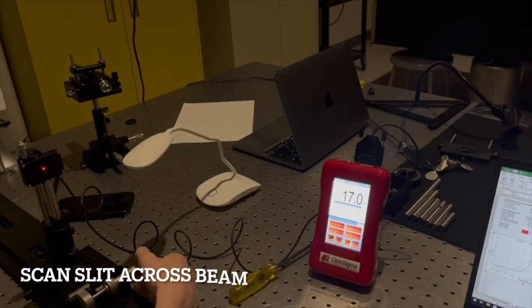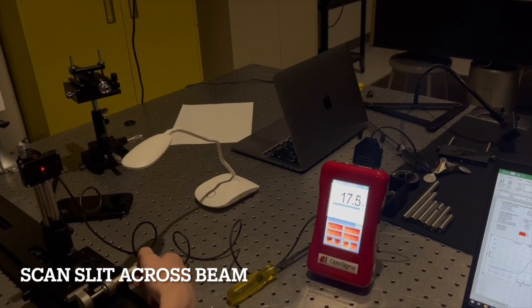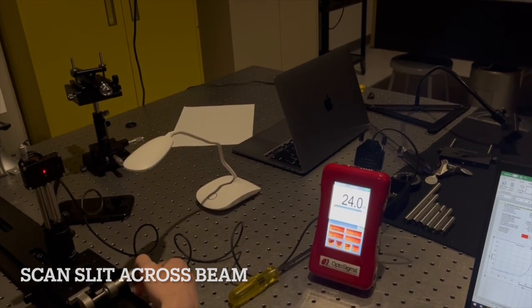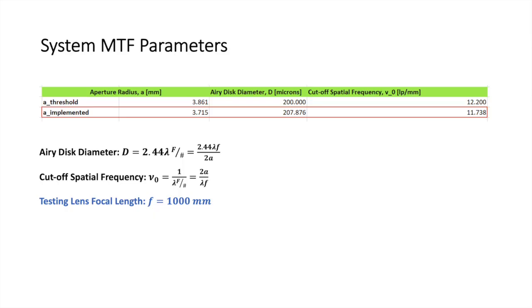To measure the line spread function, or LSF, of an optical system, in this case a long focal length lens, we effectively scan a vertical slit horizontally across the diffraction pattern produced by placing an aperture close behind the lens. For the experimental setup testing a 1000 mm focal length lens, we opted for an approximately 7 mm diameter aperture in order to ensure that we produced an Airy pattern that was measurable, or greater than 200 microns, given the resolution limitations of the equipment in lab.